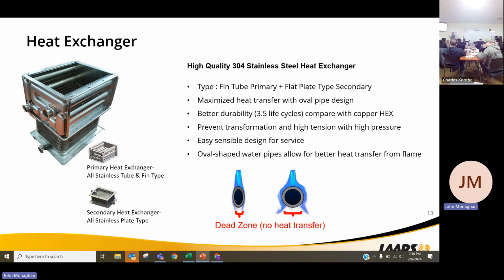Also, the secondary heat exchanger on it, which is going to be just below it, is also still going to be stainless steel. If you need to, you can get into that and clean it. The top portion of that unit comes apart just like the FT boilers do, and you can clean the mesh burner, and you can clean the heat exchanger.